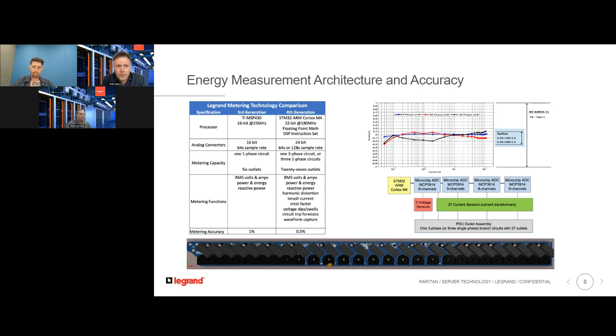And important to mention is that we have qualified our new metering circuitry according to the IEC standard 62053, and we are now able to accomplish 0.5% energy metering accuracy on the PDU inlets as well as on all individual outlets. The picture below shows one of the new G4 relay boards with support for 27 outlets, which is one of the highest density designs you can find in the PDU market today.